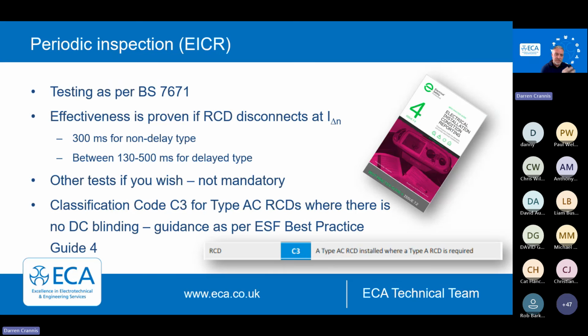But typically, if there's an AC RCD that is functioning, we'd start at a code C3. So that's an older RCD that's not got any evidence of being blinded by any DC leakage, and it's still functional upon test. You may recommend it's upgraded, but typically we're starting at C3.